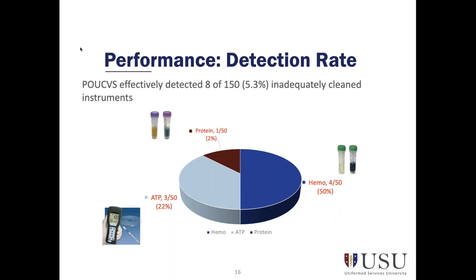All right. Performance was the second element I evaluated. The point I want to get across here is that all systems were able to detect bioburden effectively. It is essential to mention that corrections to cleaning processes and procedures were made during the testing phase. I mentioned that earlier. This could explain the low detection rate by the protein system, as it was the last system to be evaluated. All 3 point-of-use cleaning verification systems effectively detected 8 of 150 inadequately cleaned instruments. ATP detected 3 out of 50, hemoglobin detected 4 out of 50, and protein 1 out of 50. The contamination rate for non-power equipment was 3.6%, 3 out of 84, and 7.6%, 5 out of 66 for power equipment. 1 of the 50 hemoglobin tests was ruled inconclusive, as I mentioned before, and 2 of the 50 protein tests were ruled invalid.